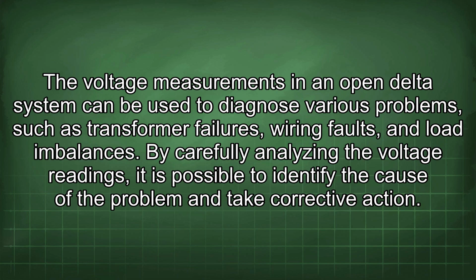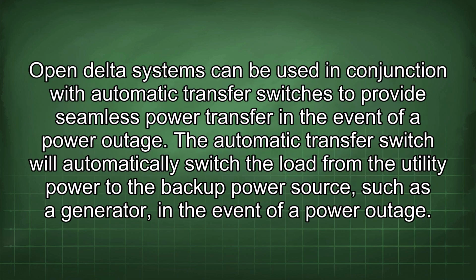The voltage measurements in an Open Delta system can be used to diagnose various problems such as transformer failures, wiring faults, and load imbalances. By carefully analyzing the voltage readings, it is possible to identify the cause of the problem and take corrective action. Open Delta systems can be used in conjunction with automatic transfer switches to provide seamless power transfer in the event of power outage.